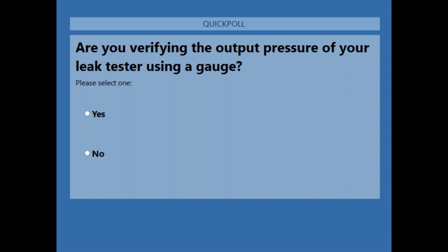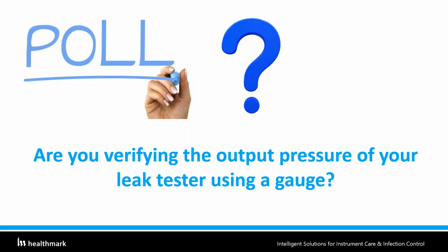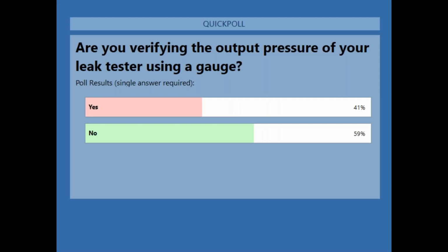Sure, yeah. What I'm going to show you in the next few slides is what really is going on if you don't do that. Again, we've been in various hospitals and found that for the leak tester meant for testing leaks on these endoscopes, I haven't seen either an HTM tag or an equipment management system. Are you keeping track of those? What's going on? So really that was to see whether somebody is testing those leak testers that are supposed to help if the device is in good shape.